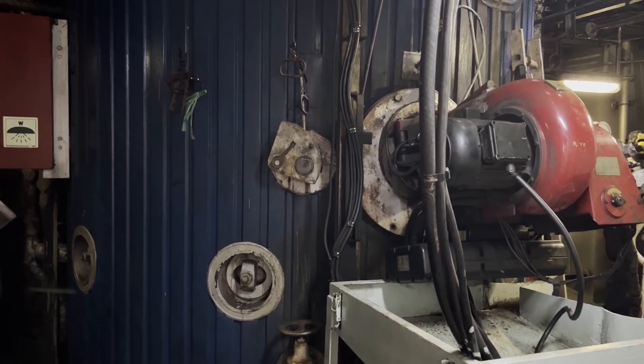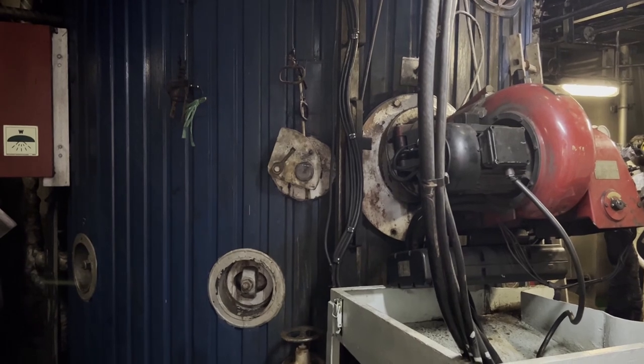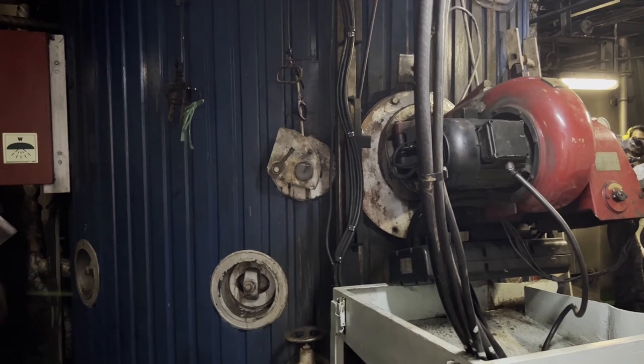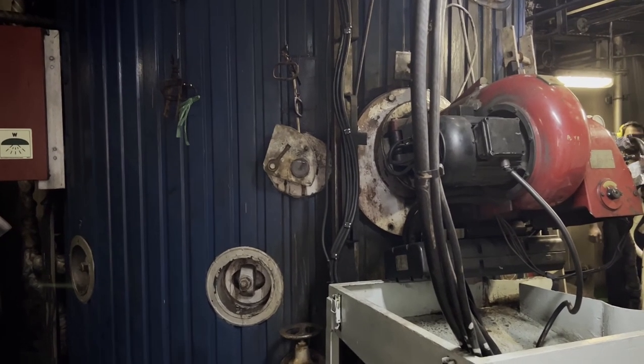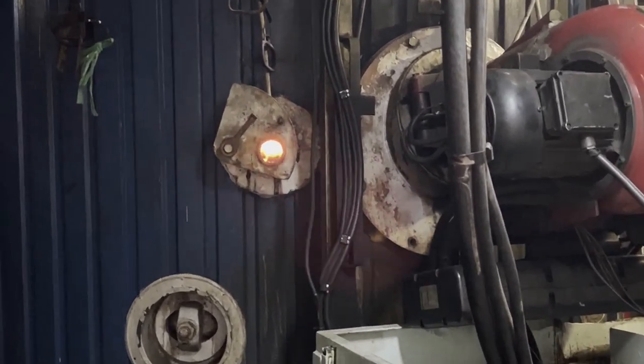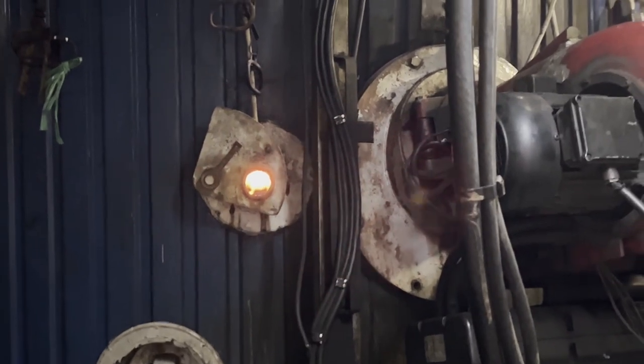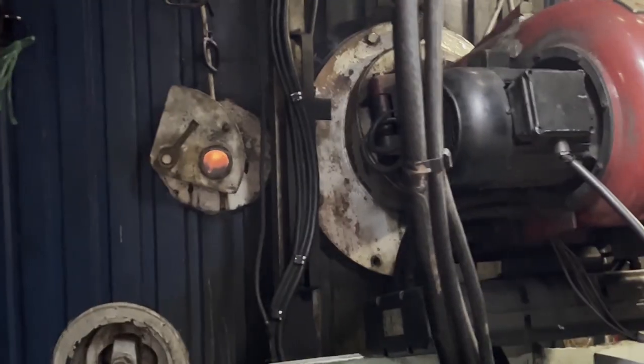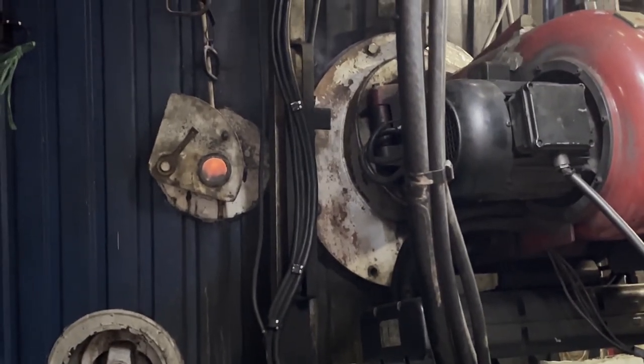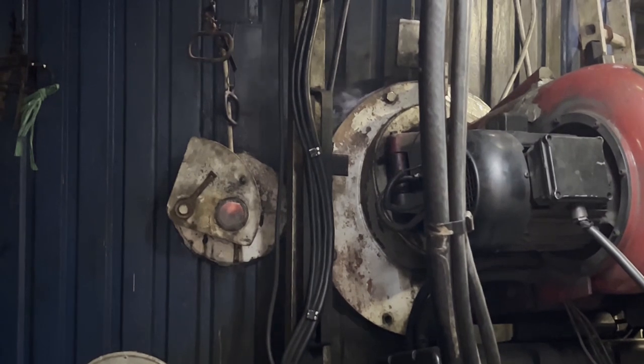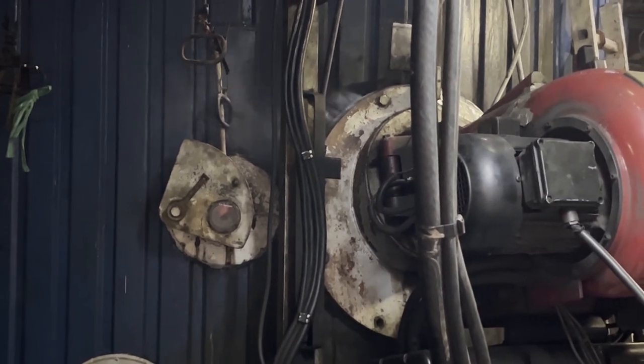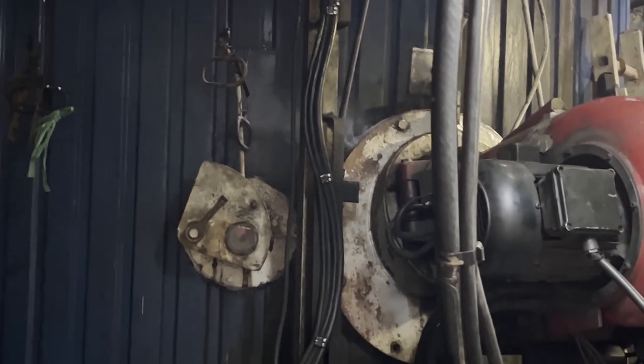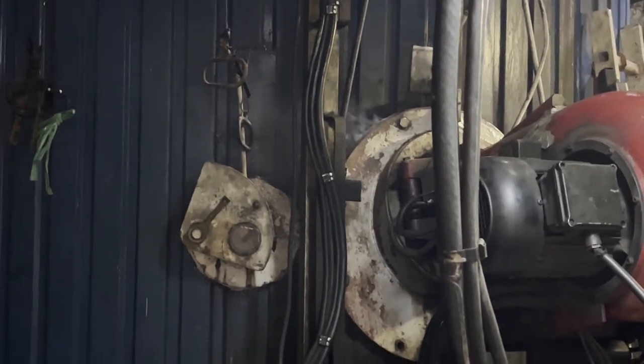Now I want to show how a backfire will occur and what the indications are. We are firing the boiler. In this case you can see that out of four, two are already choked. I'm just giving a small fire. You can see the smoke is coming out through the flange area.